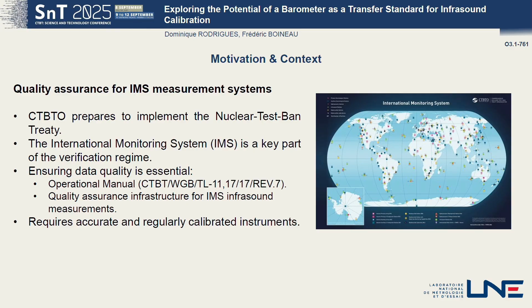The infrasound measurements within the IMS must be traceable to the international system of units, and this metrological traceability means different needs at different levels. On the top, we find the first realization of the unit, the primary reference standard, which is usually established by a national metrology institute. At lower levels, we find the accredited labs and expert labs, which require working or traveling standards in order to perform secondary calibration of sensors, usually by comparison against such a working standard.